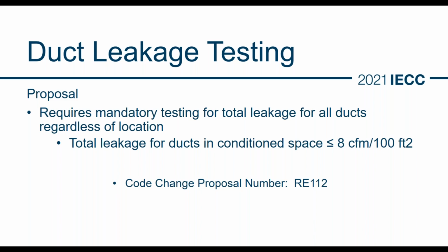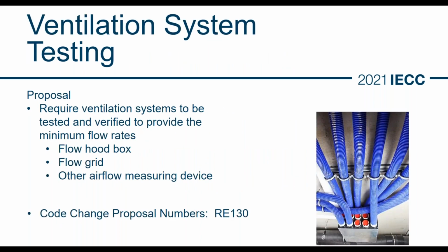So you could have a leakage rate up to 8 CFM per 100 square feet. What this would do is essentially make sure that the conditioned air from the mechanical system actually has a much better chance of getting to the space that you're trying to either heat or cool. So this again, I think, is an important one for the Northwest. I know there's a lot of testing being done in the Northwest from a duct leakage standpoint, and I think this is an important requirement to make sure that ducts don't leak regardless of where they are. So again, this is going to be RE112. If we can go to the next slide, please.